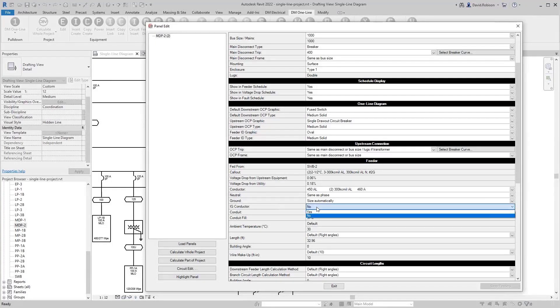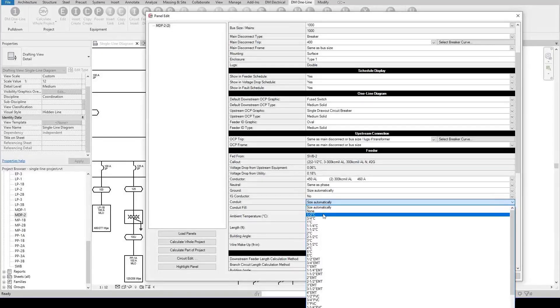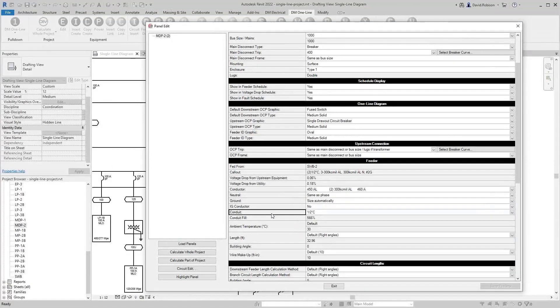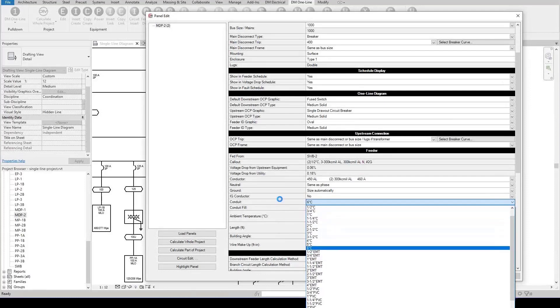You can add an IG conductor if needed, and specify a specific conduit size. We default to sizing the conduit for 40% fill based on the wires chosen, but you can adjust it. The software lets you be the engineer and choose whatever you want — it will flag if the conduit fill exceeds 100%, but will still allow you to specify it.